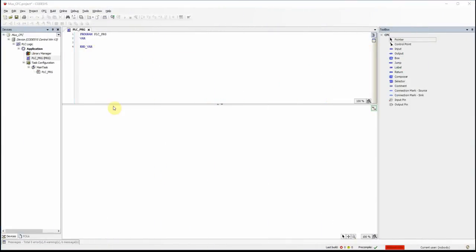Hi everyone. In this short video I will explain how to use the MUX function or operator in CFC programming language within the Codesys environment. I have already created a project called mux_CFC and selected CFC as the programming language, which is why you see this kind of toolbox in the programming environment.